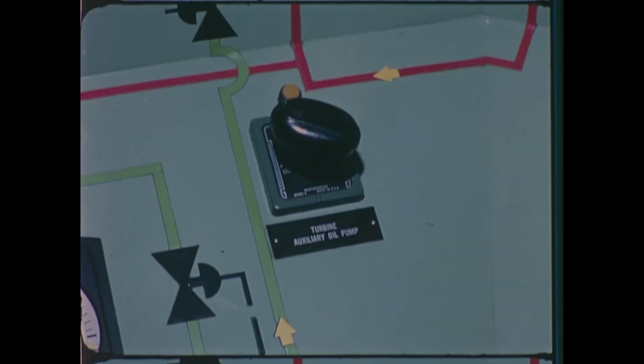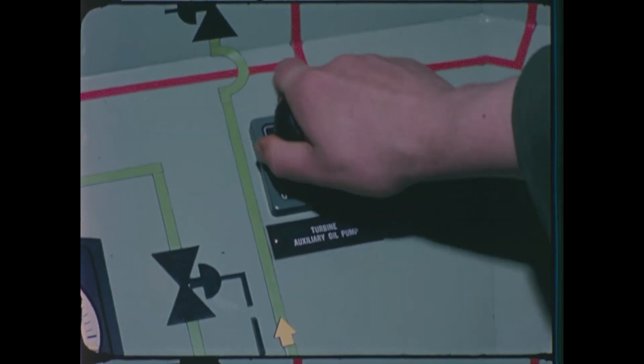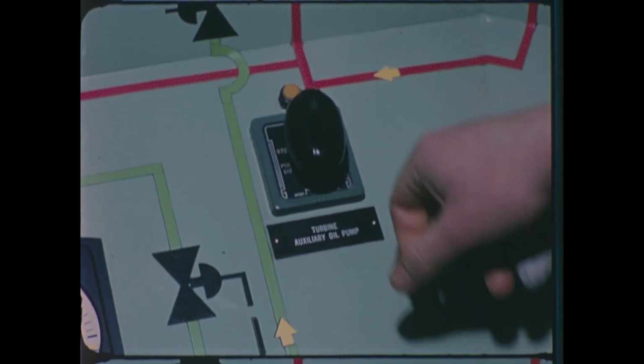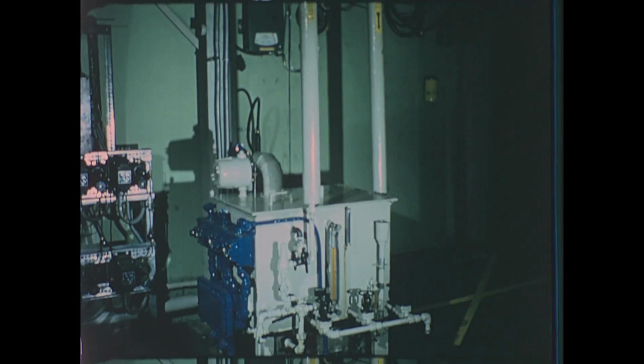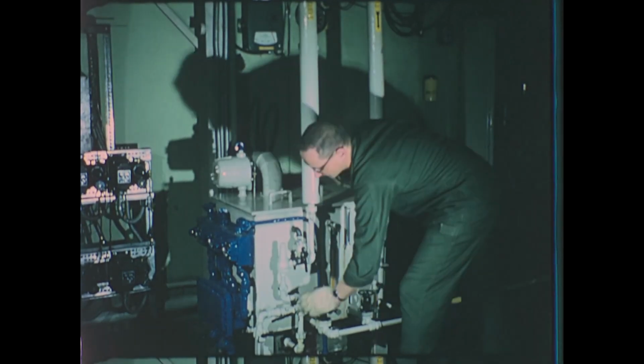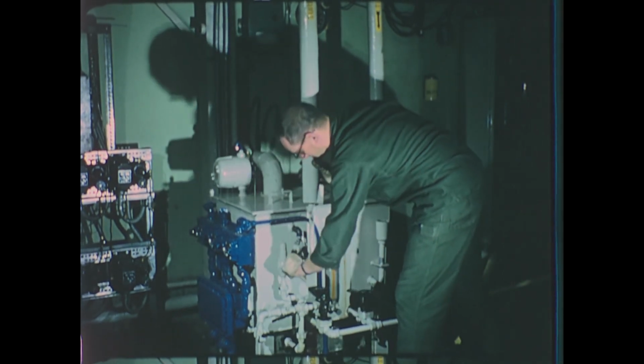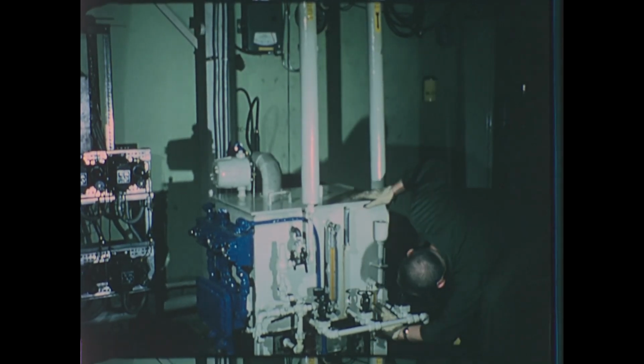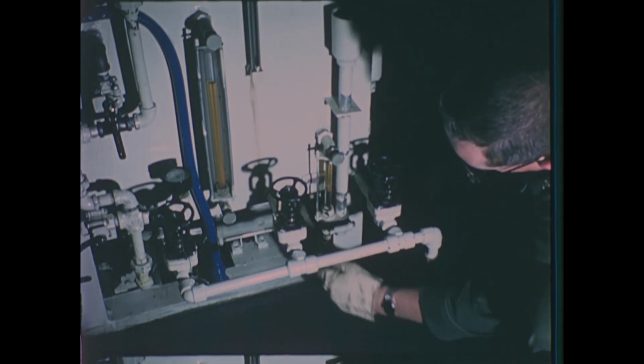At the console, the operator turns on the turbine auxiliary oil pump. Oil must be pumped for 2 hours prior to rolling the turbine to raise the temperature and to process it through the lube oil conditioner shown here. The equipment operator checks water level, pressure, and flow through the conditioner.